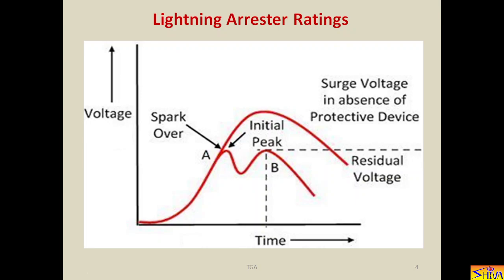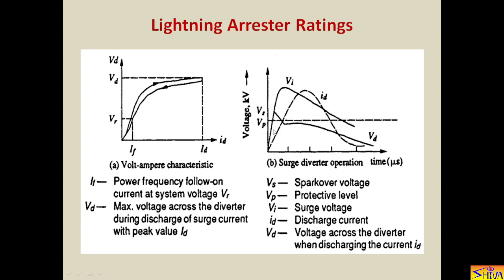So in no case the residual or discharge voltage should exceed the impulse spark over voltage of the lightning arrestor. Otherwise, if it is more, then it will damage the protective device insulation. Now in this diagram I have also shown the discharge current. So this is VI, that is the surge voltage. At this point lightning arrestor has sparked over. So from this point onwards the discharge current starts flowing. It attains some peak value. So corresponding to this peak value there is maximum value of the discharge voltage. So this entire is discharge voltage, but we are basically interested in this maximum value. So that maximum value is called as discharge voltage or residual voltage, and this current is called as maximum discharge current.